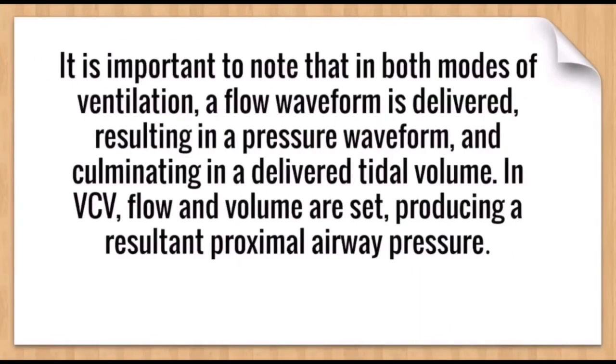Now it's important to note that in both modes of ventilation, a flow waveform is delivered resulting in a pressure waveform and culminating in a delivered tidal volume. In volume control ventilation, flow and volume are set, producing a resultant proximal airway pressure. So in volume control, we have volume set, flow set, and that will result in the proximal airway pressure depending upon the compliance and the airway resistance.